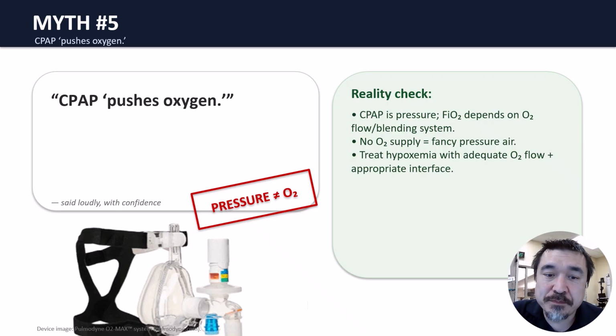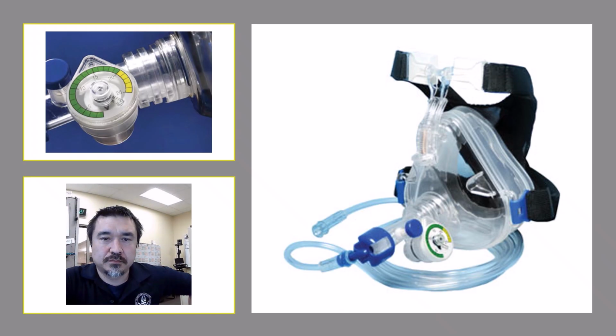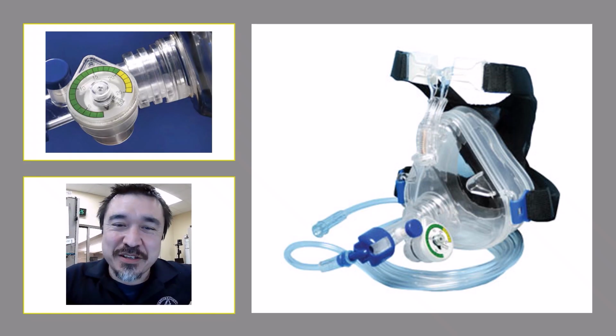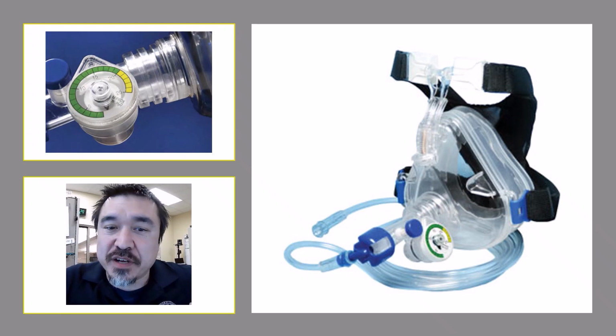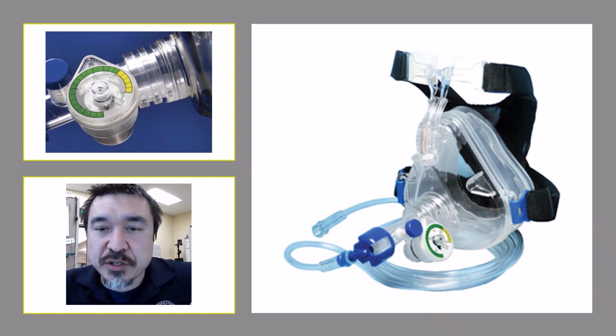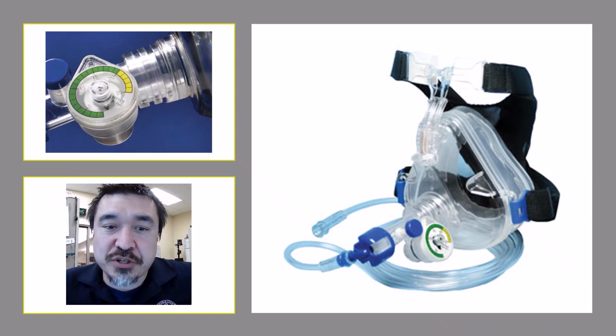It's not making you take a breath, but it is keeping the alveoli open. Hey, what do you recommend for CPAP? Oh, hey, I'm glad you asked. We spent quite a while researching devices and we landed on Mercury Medical's FlowSafe 2. This device is flow powered, Venturi-like driven, creates a pressure through the entire breath cycle, has an actual air entrainment and anti-asphyxiation valve, and an overpressure pop-off safety. It's not run by a turbine or an electric fan, and is able to give off high FiO2 and flow to cover a higher spread of patients.